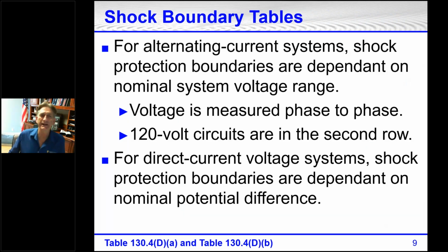All right, so for alternating current systems, shock protection boundaries are dependent on nominal system voltage range. Well, how is it measured? Voltage is measured phase to phase. In this table, we have a footnote that references 120 volt circuits only, and we'll look at that in a minute. For direct current systems, shock protection boundaries are dependent on the nominal potential difference for the voltages.